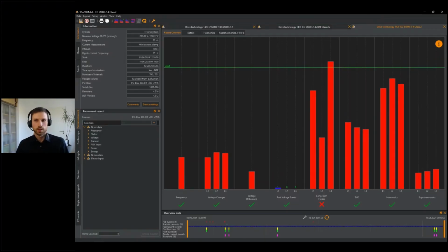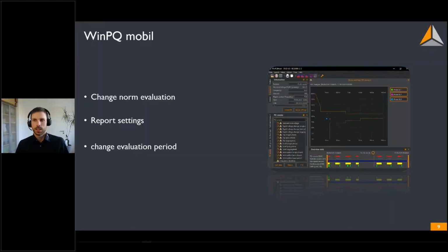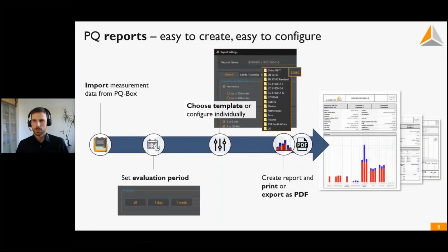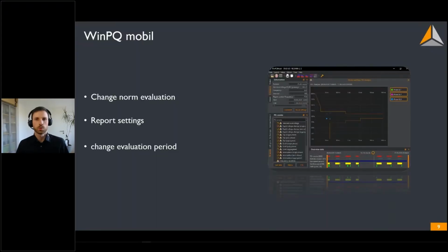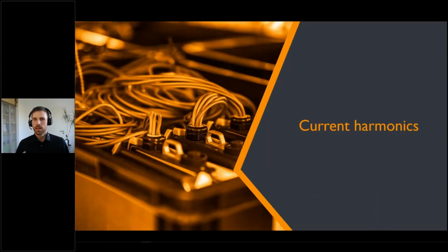So I was talking about the harmonics. Now I want to talk about current harmonics, the second point on the agenda, because voltage harmonics are covered by power quality standards for the public and industrial grid. Current harmonics are different; other standards deal with current harmonics.